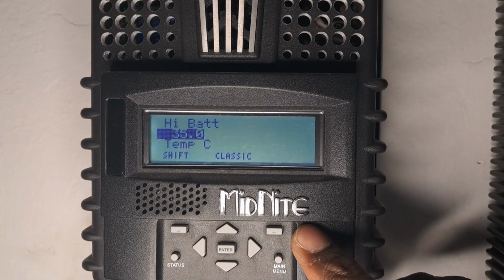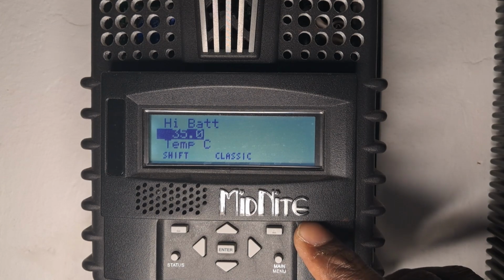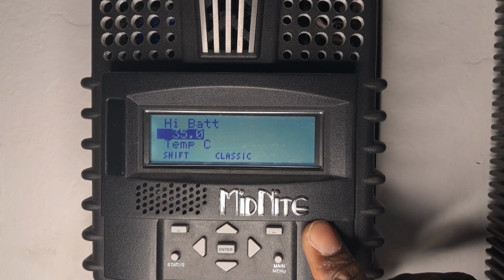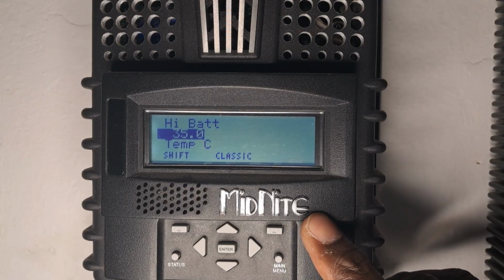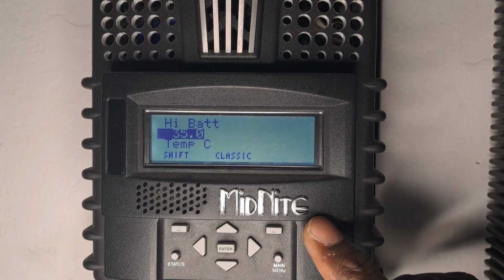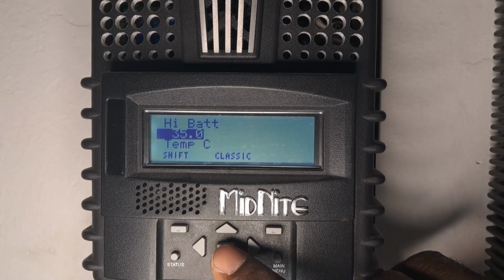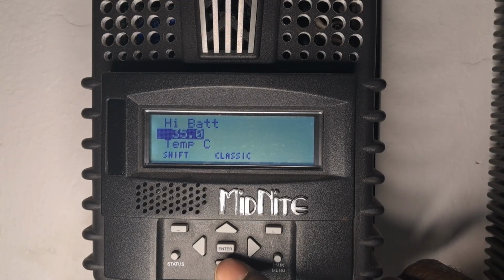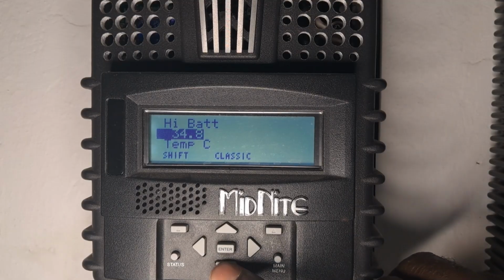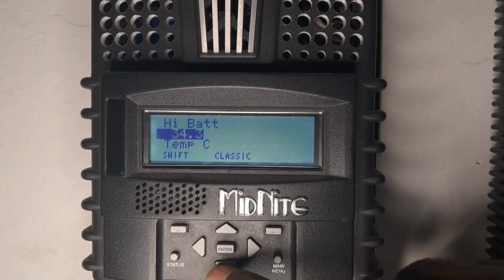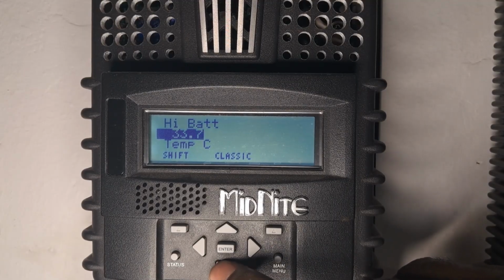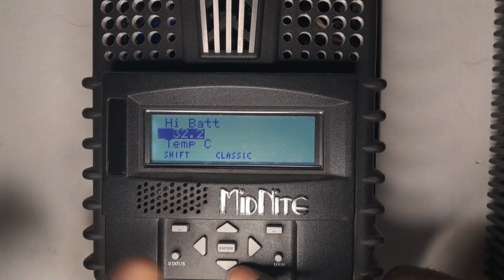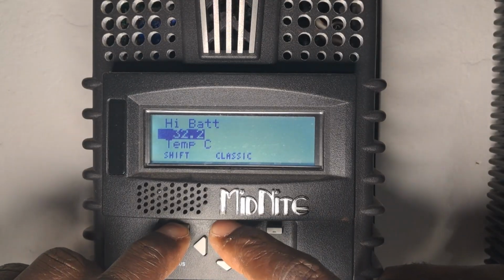By default, this value is set at 150 or 170, in degrees Celsius. You want to take this number down to a suitable temperature for your battery bank or setup. I've already changed mine to 35 degrees Celsius. To change the temperature, use the down or up arrow. The down arrow alone moves the decimal number, and holding shift with up or down moves the whole number.